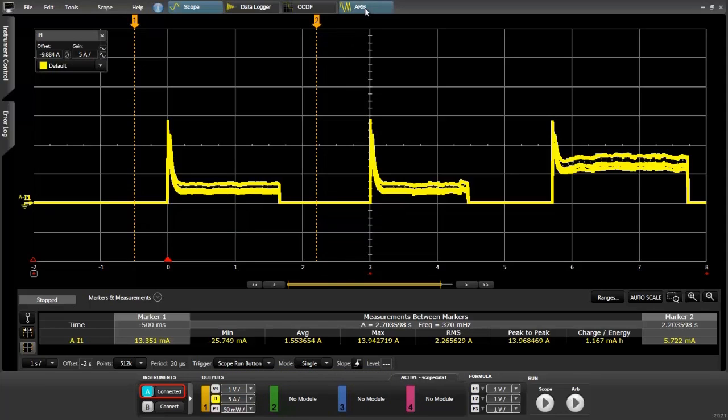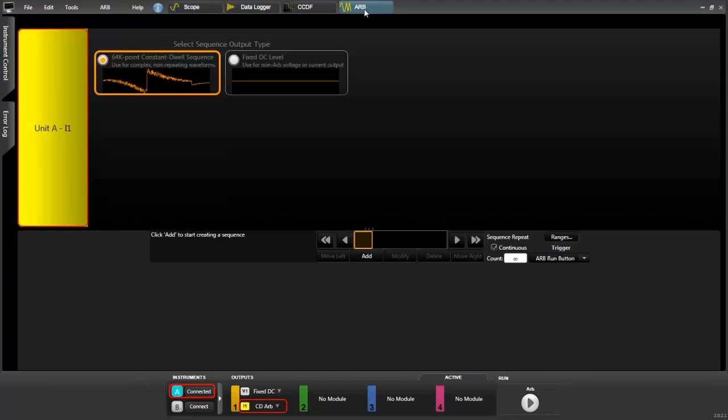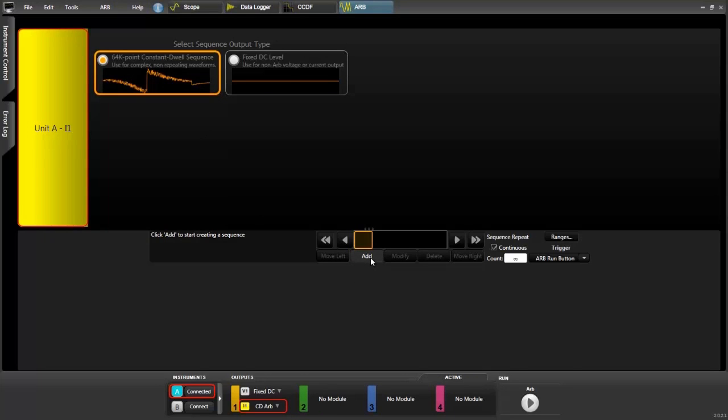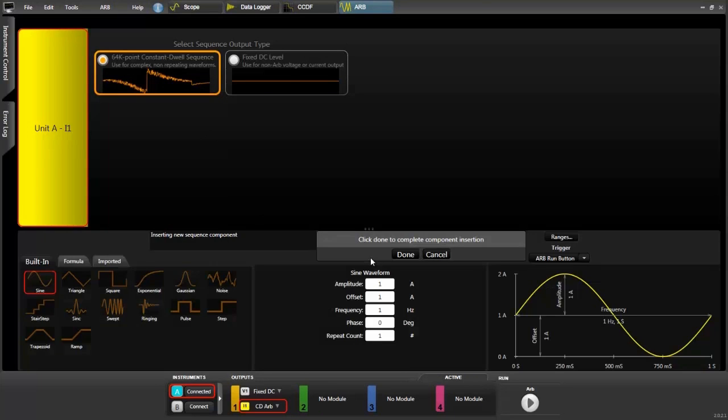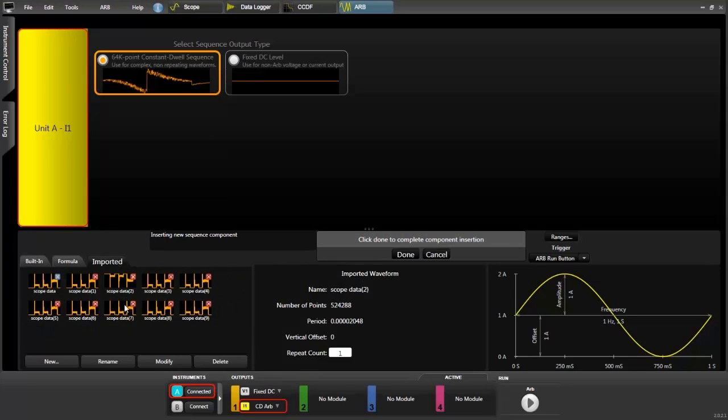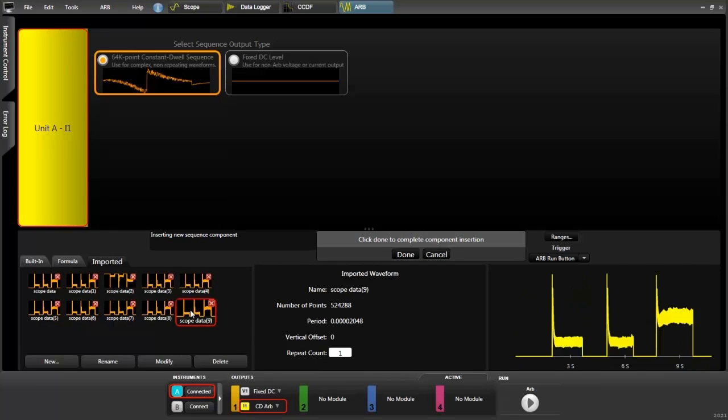Then all we need to do is go to the ARB section of the software and set everything up to have a current waveform. We choose the output that we want, click add. There are three different ways to create waveforms. We're going to use the imported waveforms. Scroll down to the one we want. Here it is. It's the scope data from our capture.